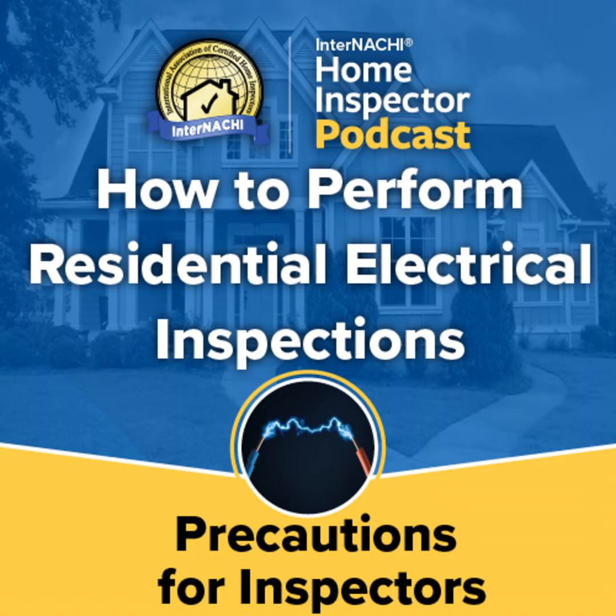Fourth, use the appropriate tools. According to InterNACHI's standards of practice, inspectors are required to test all ground fault circuit interrupter receptacles and circuit breakers observed and deemed to be GFCIs using a GFCI tester where possible. Make sure your tester is working properly before your inspection appointment. An infrared camera is also a tool for helping to detect hotspots during the electrical inspection.